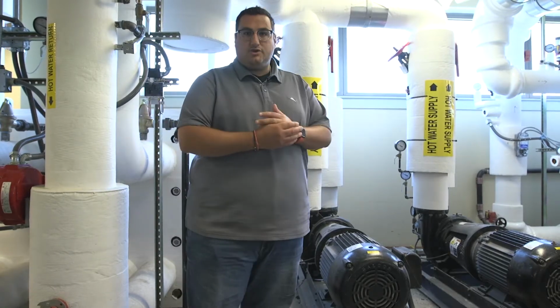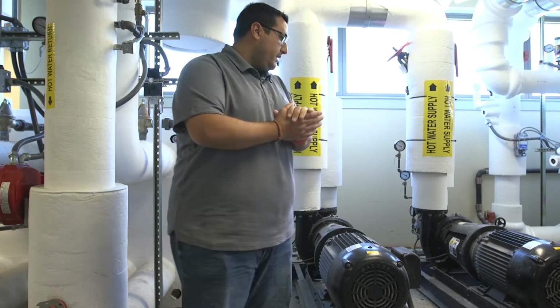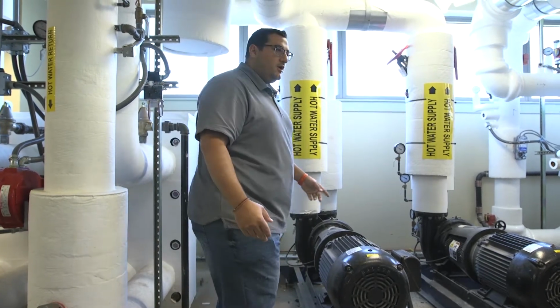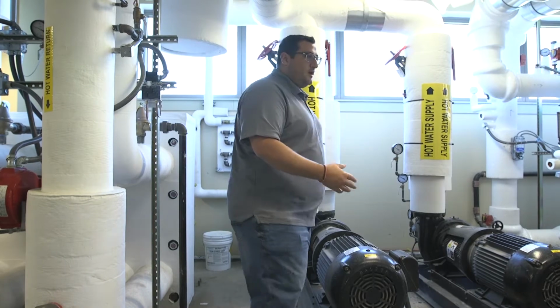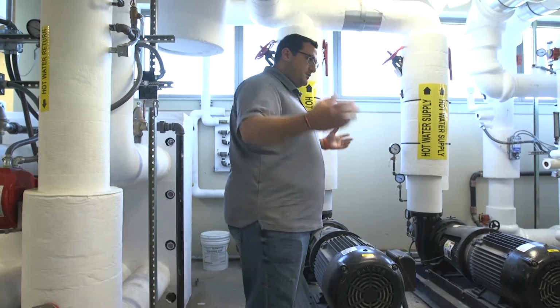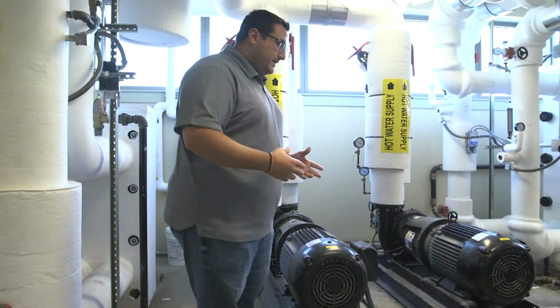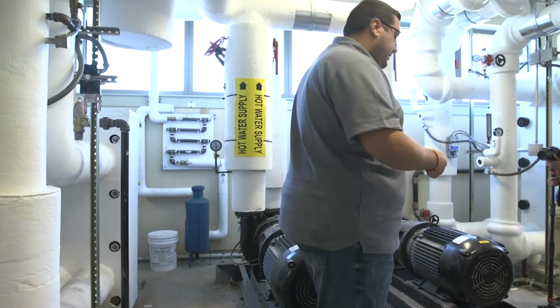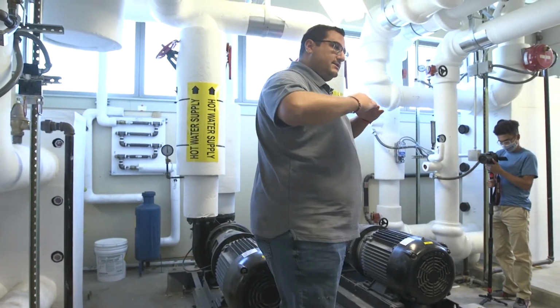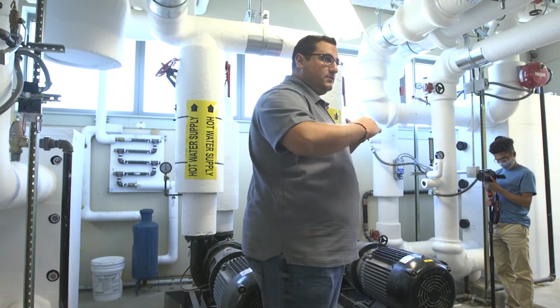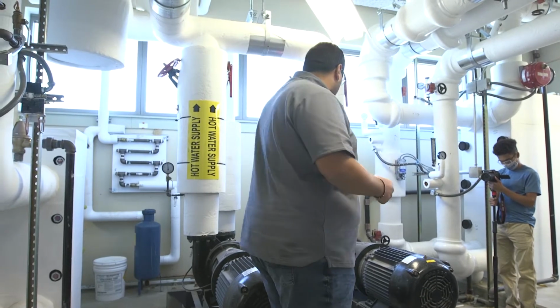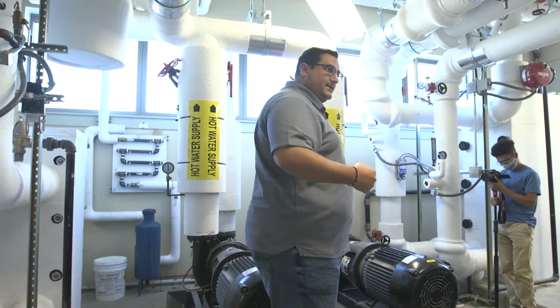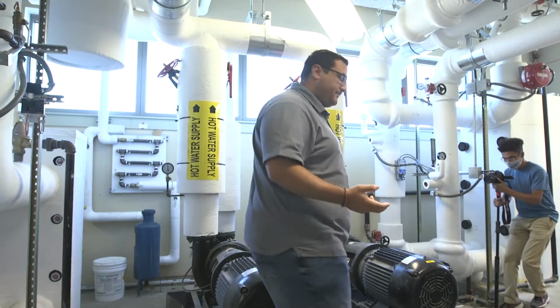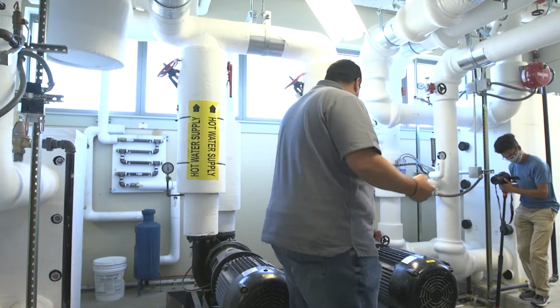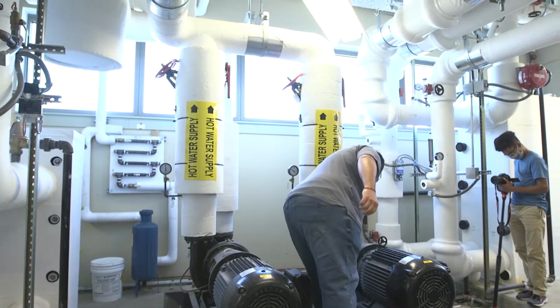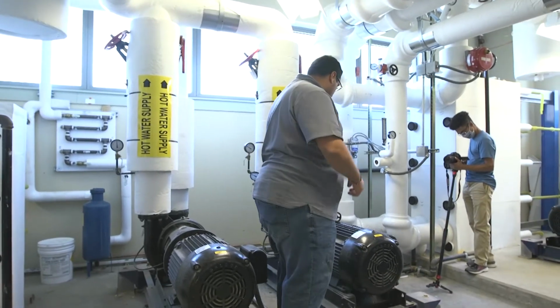We're doing pump training. So we're going to start here with these PACO pumps. These are called PACO close coupled end suction pumps. The reason they're called close coupled is the coupling; there's no laser alignment needed. So they're already self-aligned once installed. End suction because they suck from the end and they discharge from the top. That's what's called an end suction pump. Very basic. Obviously, this is the suction, this is the discharge, the pump runs.